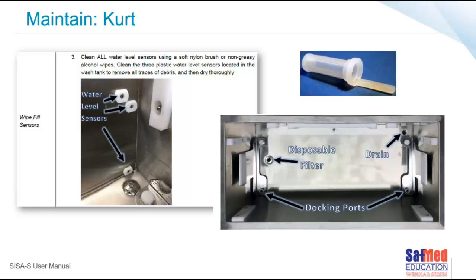And this sensor will pick up if the water is bypassing, if the fill sensor failed, or the flow rate is coming in too quickly, as we spoke about earlier, and it will trigger the overflow sensor. If all these sensors fail, you have the overflow pipe, which is a safety feature.